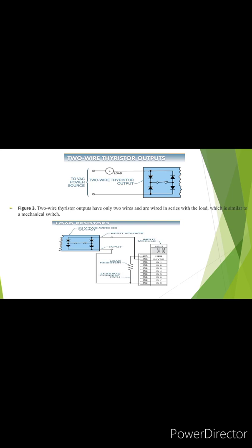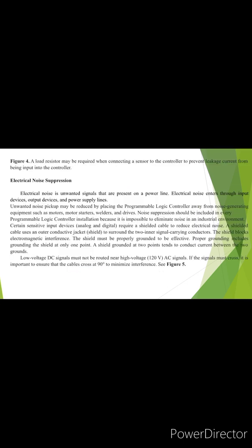Two-wire thyristor outputs have only two wires and are wired in series with the load, which is similar to a mechanical switch. Load resistor. 24 volts, two-wire DC output. Input voltage. Input module. Input. Load resistor. Leakage current path. Figure 4. A load resistor may be required when connecting a sensor to the controller to prevent leakage current from being input into the controller.